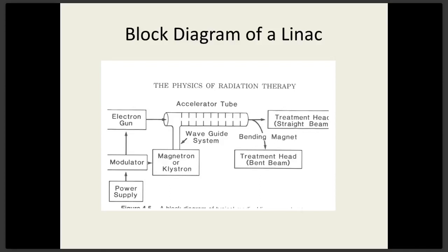If the phase of the microwave is off even a little bit so that the electron doesn't arrive at that central aperture at just the right point when the voltage should switch from minus to plus, the electrons will not get accelerated and the machine just sits there and hums and you get an undervoltage fault. So phasing, radio frequency control, automatic frequency control, all very, very important. 3/4 of the machine is nothing but a microwave generator. Once the electrons hit the target and radiation is produced, then you have the beam shaping and beam control mechanisms that we're going to talk about in a little while.